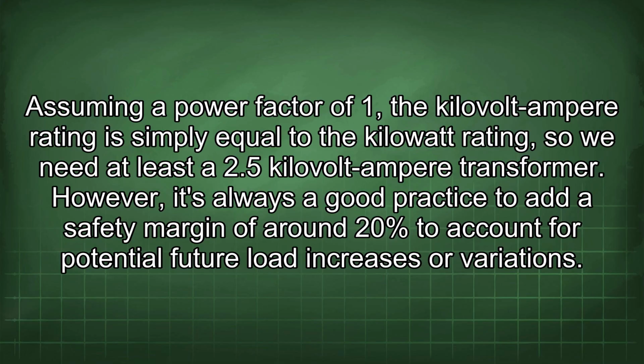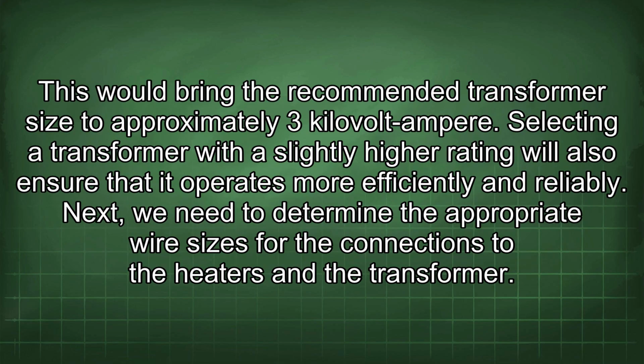However, it's always a good practice to add a safety margin of around 20% to account for potential future load increases or variations. This would bring the recommended transformer size to approximately 3 kilovolt ampere. Selecting a transformer with a slightly higher rating will also ensure that it operates more efficiently and reliably.